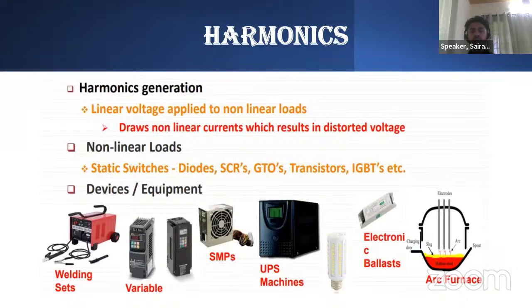The linear voltage applied to non-linear loads will lead to harmonic generation. The non-linear loads are such as diodes, SCRs, transistors, IGBTs. The equipment that are familiar in generating harmonics are variable frequency drives, UPS machines, ballasts, arc furnaces, welding sets, etc.